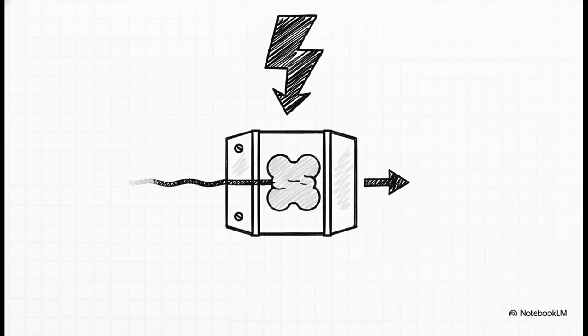Okay, picture this terrifying scenario. Imagine a massive short circuit on the power grid. The protection relay works perfectly, it detects the fault and fires off a trip command, but then the primary breaker mechanically jams. Its contacts are literally fused together, and that massive, destructive fault current just keeps on flowing.